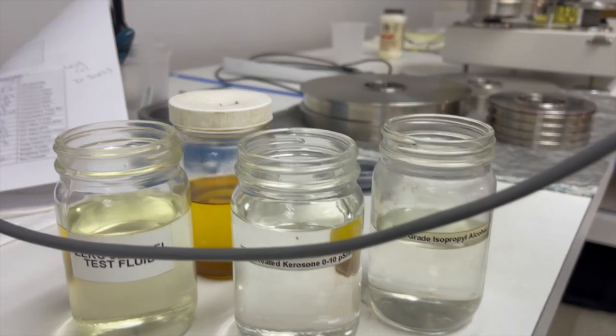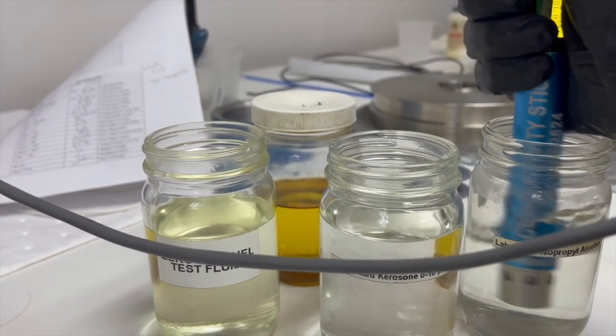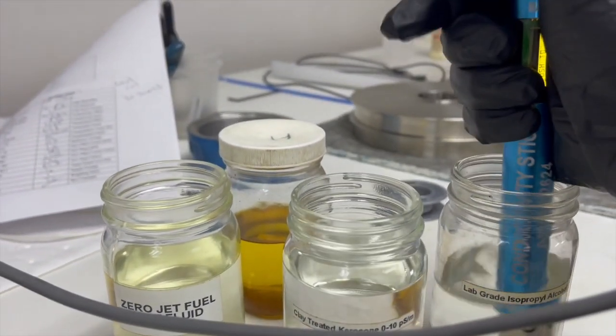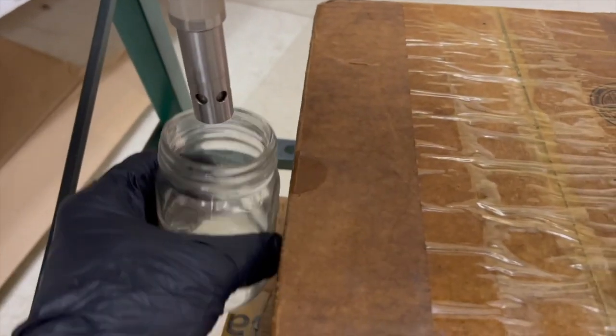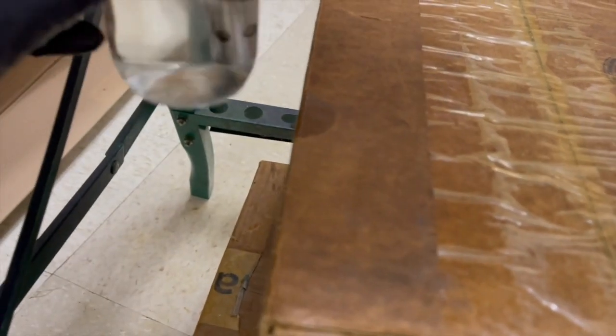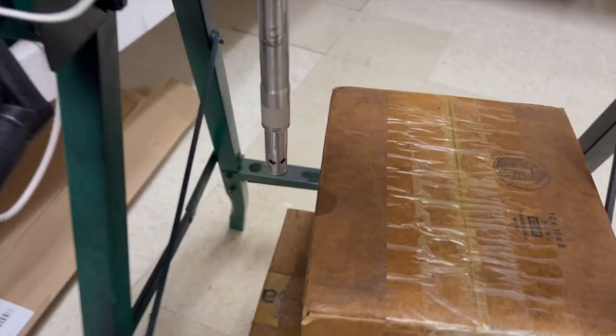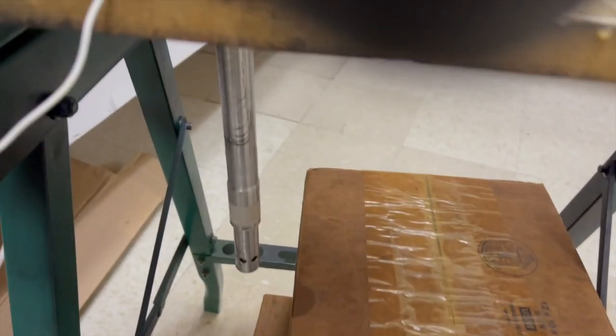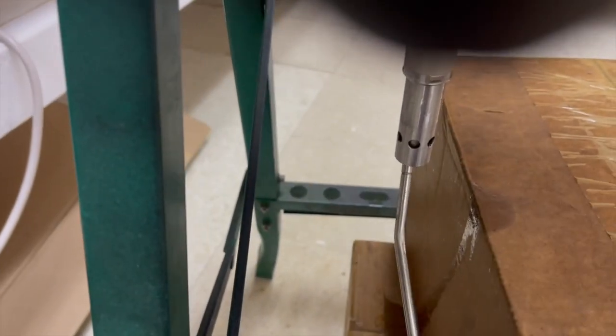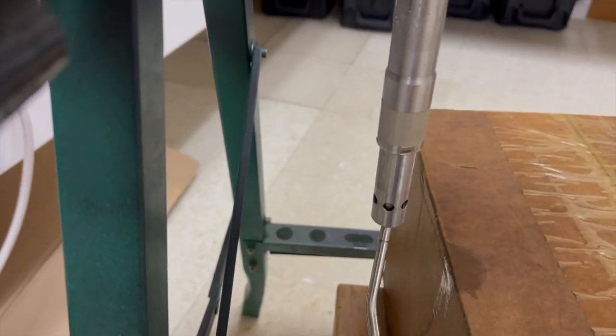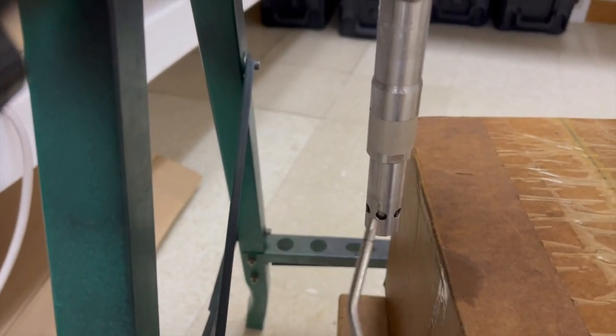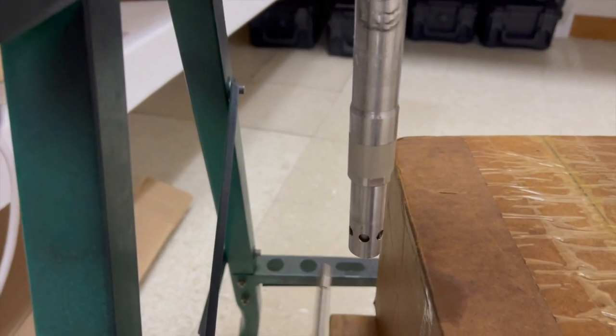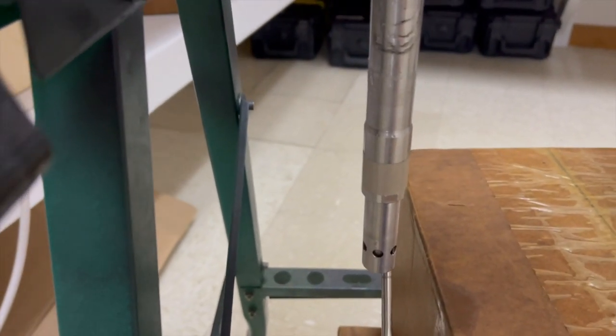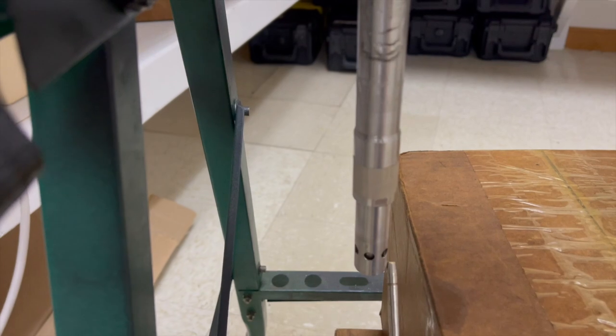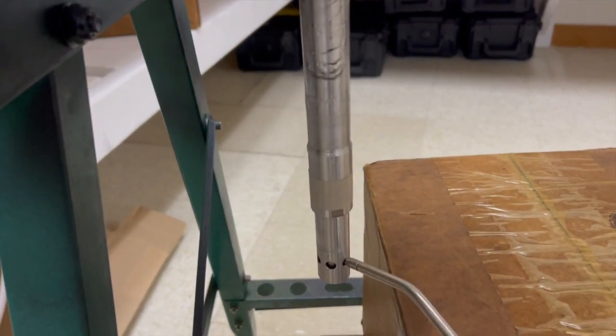One of the first things you want to do is make sure that you clean the sensor tip off in your lab grade isopropyl alcohol. You want to do the same with the inline sensor. Dip in isopropyl alcohol, clean it off, and then blow off the sensor tip. Make sure you get inside the groove. Make sure it's completely dry. You don't want any of the isopropyl alcohol still on there.